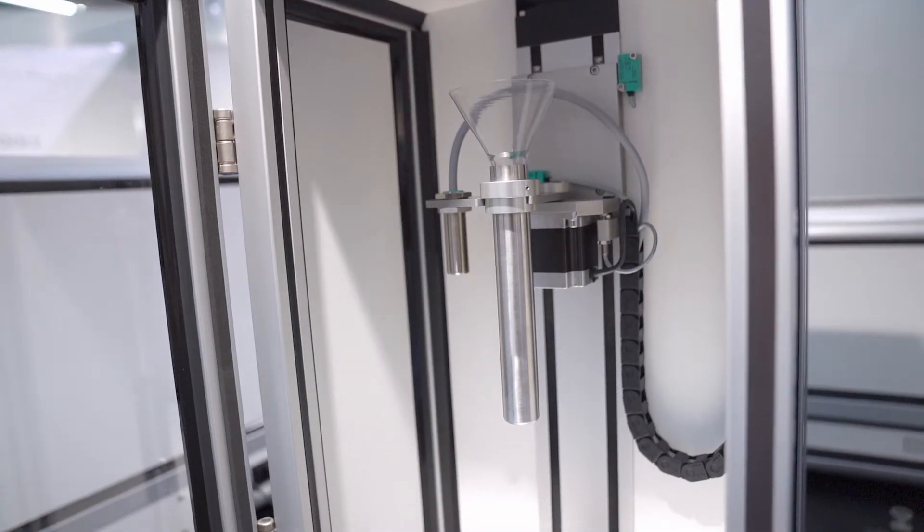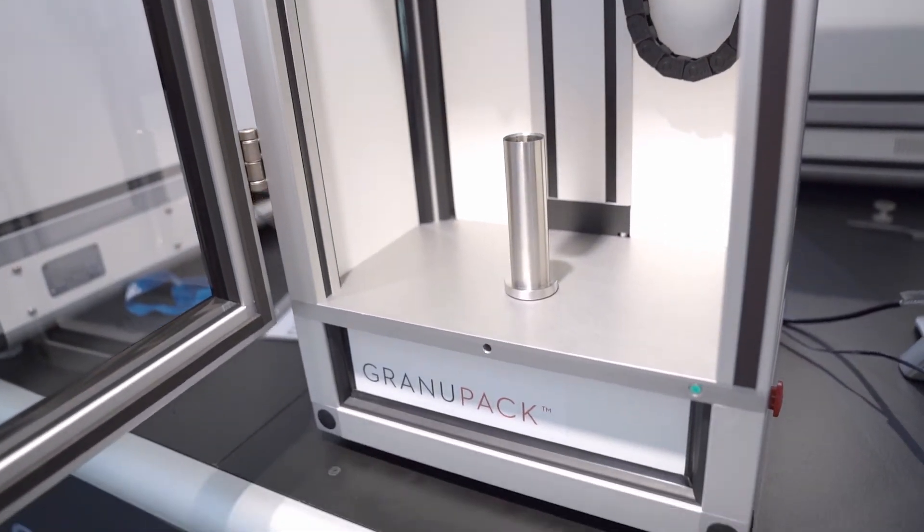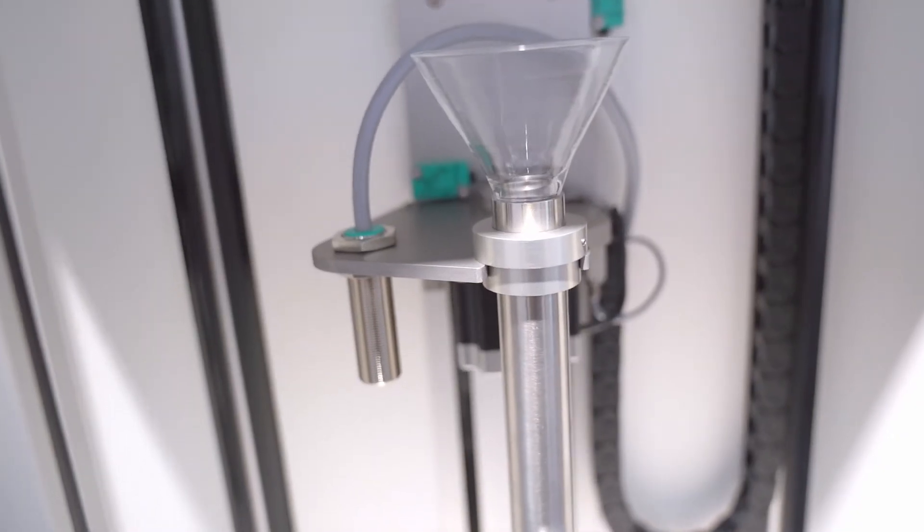This is the GranuPack. The GranuPack is an instrument that is very unique. It will provide you information about the compaction of a material during the process. What is very unique about this instrument is that we can measure the density after each tap, after each compaction step.